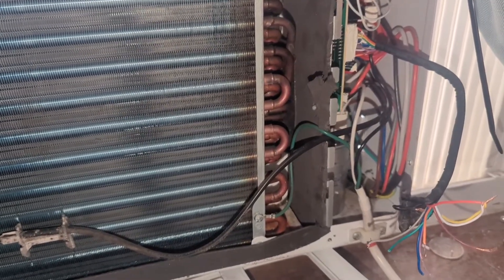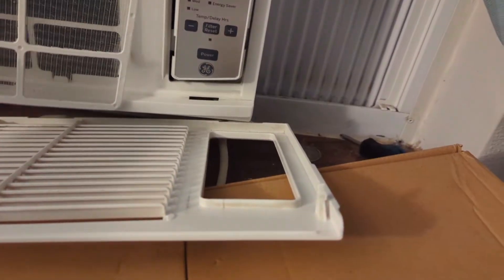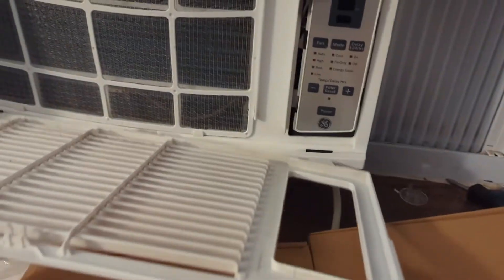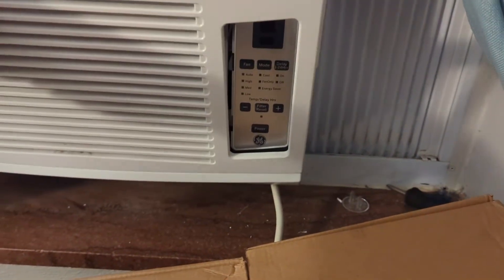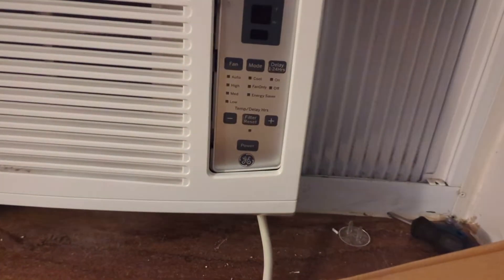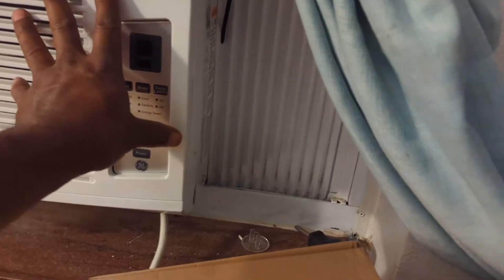When I get this control panel I'll replace it and show you that it's back to normal. Put everything back together so it doesn't get lost — here's the filter; we took that out and cleaned it because that's the right thing to do. The control panel didn't sit in there right, but the panel wasn't down all the way and the screw wasn't in it — that's why. You plug it in, hit the reset button, and see that it works.